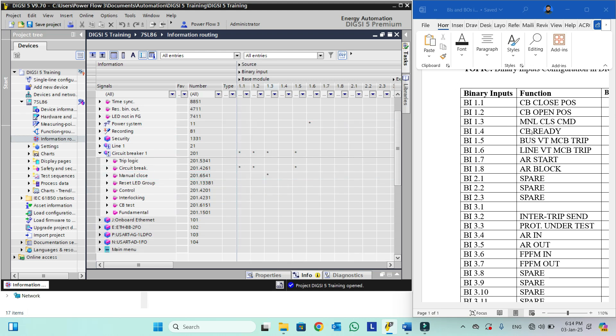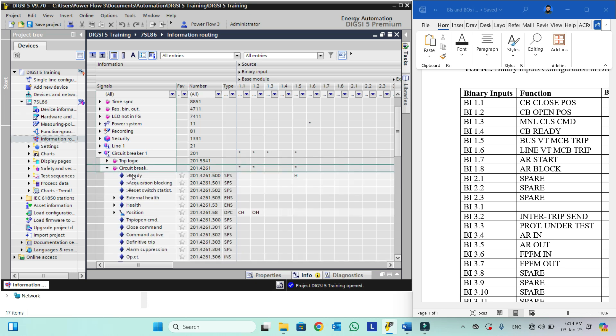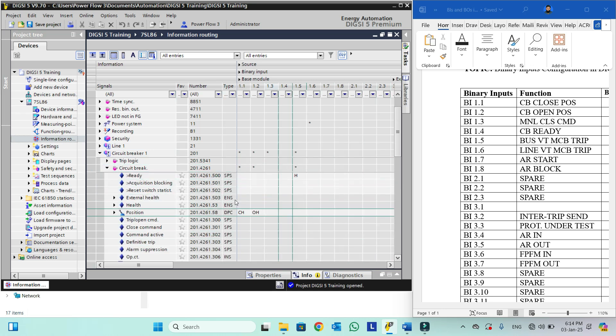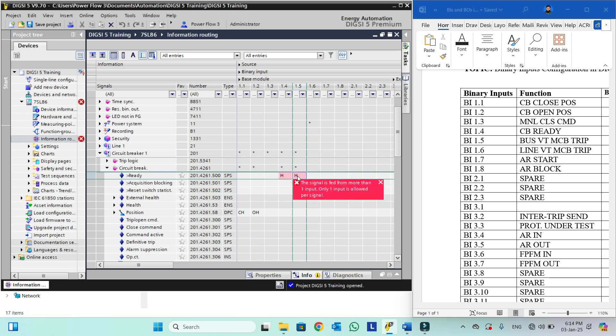Now the fourth one is CB ready. We will go into the circuit breaker function group. Here you can see the CB ready input is available — this is 1.4. You can see that at 1.5 it is also available, but two binary inputs cannot be assigned for CB ready; it should be one input. So we will delete number 5.